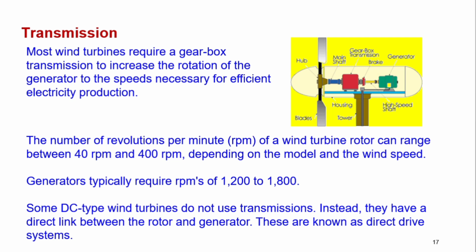Transmission: this is used to transmit the mechanical power generated by the blade to the generator. The number of revolutions per minute of the wind turbine rotor can range between 40 rpm and 400 rpm depending on the model and wind speed. Generators typically require rpms of 1200 to 1800.